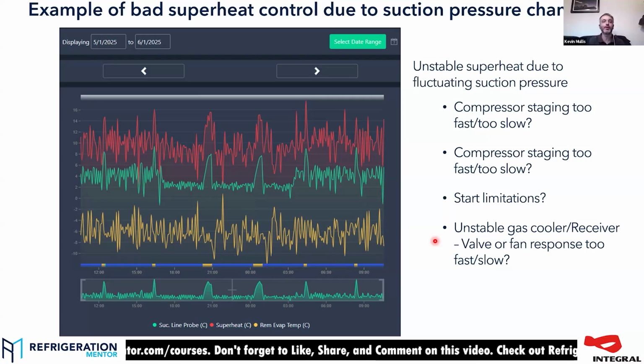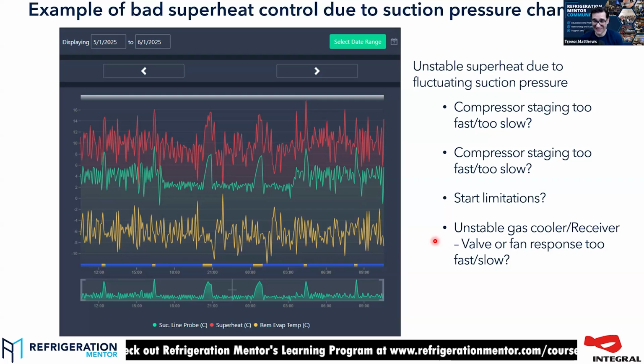Especially when you're operating transcritically, that is a heck of a lot of vapor coming into the suction line. I'm sure many people on here who work with CO₂ have seen, in the summer, if the rack is heavily transcritical on a warm day, you can switch all the cases off and the rack will continue running for another half an hour, because it's just circulating the heat the compressors are generating through the system. And it won't stop, and you often have to manually intervene to tell it to calm down. But it's a heck of a lot of load, and that can have a big effect on the suction pressure. So with CO₂ you need to consider that maybe the cases are absolutely fine, and maybe the compressor staging is absolutely fine, but maybe something further up the system is causing it to be unstable.